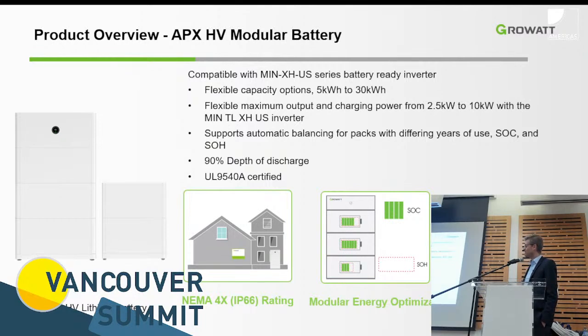With the topology that every battery module is on its own and has its own DC to DC stage, you have 2 or maybe 3 major advantages. Each module controls itself, and if you have, let's say, aging effects and degradation, one module might be more affected than another module. The modules are adding power to the same DC bus, which means each module is only giving as much power and current as it can based on its degradation state or its thermal state. If it's very hot, for example, it will limit the output power on its own, while another module that is not as hot or didn't degrade as much will just contribute more at that scale.